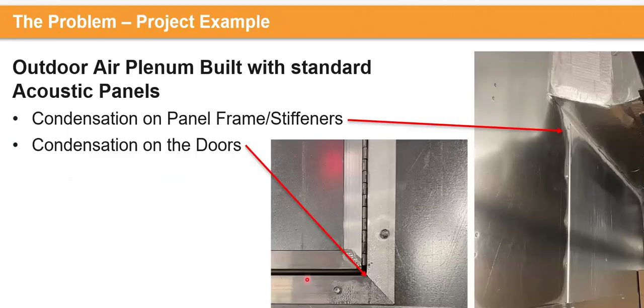Here's a practical picture of what the issue is. Right here at the corner of this door, through the frame, you do have the surface temperature being much lower than the dew point. So you do have sweating or condensation right at this point. This might not be the biggest issue just because it's a little bit of water, but once you begin to have more extreme cases where you have ice buildup around the joints, this becomes very concerning. You have the expansion of water through ice, and then you could have the derating of your connections. If these plenums are pressurized, you could likely have the possibility of failure at these connections and it could collapse.